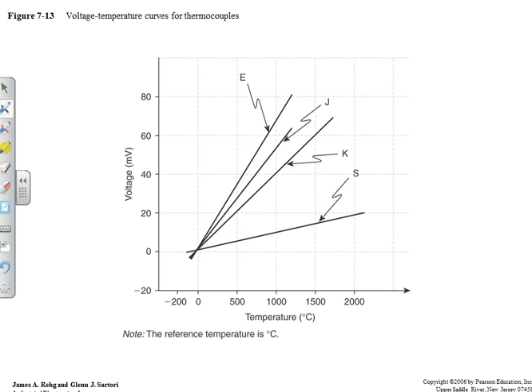These are thermocouples. What a thermocouple does is I take dissimilar metals, weld them together, and they give me a voltage. Depending on what I make the material out of will depend on the slope of the curve for voltage versus temperature. That's not a whole lot of volts, right? At 1,000 degrees, I'm getting all of 40 millivolts. That doesn't seem like a lot, does it?